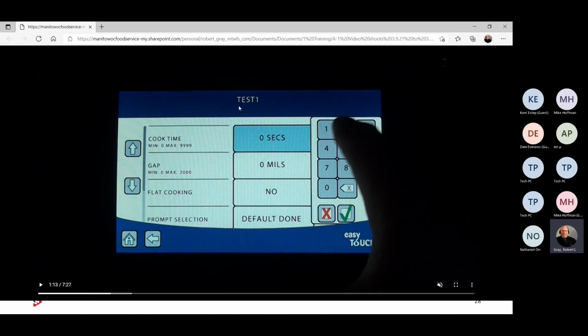At this point, you have your test, your recipe name, and you have to do your cook time. You have to enter in the gap. Now keep in mind the gap is in mils, which means if you want to give it a relationship, 1,000 mils is equivalent to 1 inch. You have to turn around and select it. Is it flat or clamshell? If it's no, it means it's clamshell. Prompt selection: what do you want it to say after the cooking cycle is complete? So let's go ahead and watch.